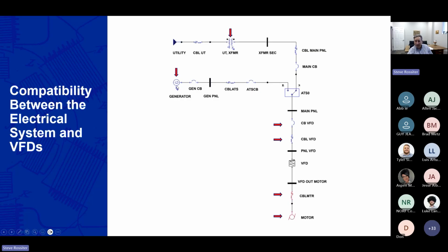Following a standby generator, the same kinds of problems are going to be potential in the circuit back to that generator, where now you've got a voltage regulator following the voltage, which could be distorted now and could go into an instability problem if there's too much harmonic distortion. And we have lots of opportunities to solve problems associated with a VFD being implemented on a standby generator, which needs to consider how we go about that and make sure that's not going to be a liability of reliability failure.